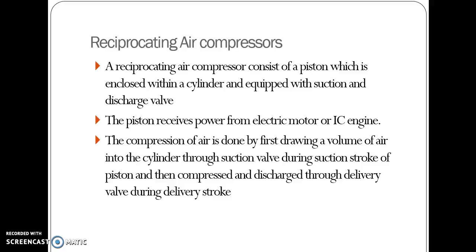A reciprocating air compressor consists of a piston which is enclosed within a cylinder and equipped with suction and discharge valves. The piston receives power from an electric motor or IC engine. Compression of air is done by first drawing a volume of air into the cylinder through the suction valve during the suction stroke, and then compressing and discharging it through the delivery valve during the delivery stroke.